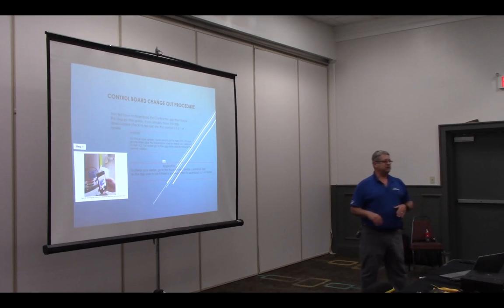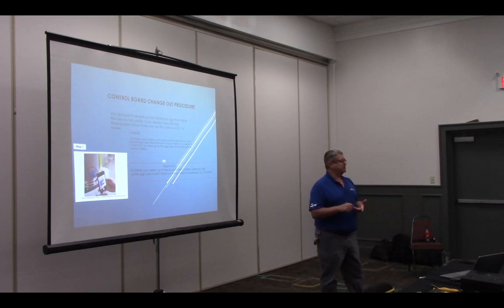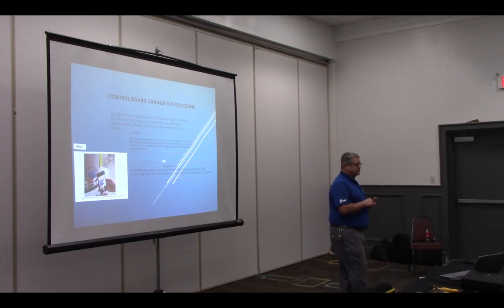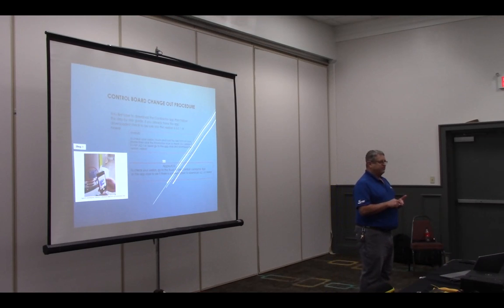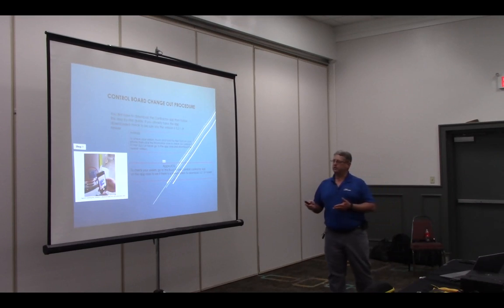If you put any of this equipment in, I would recommend updating the boards prior to installing them. With the 15 and 16 SEER, if you install a 3-ton or a 5-ton, you have to update the outdoor board, because there have been updates to those two pieces of equipment, the 3-ton and the 5-ton, 15 and 16 SEER straight cool or heat pump. Okay? So we're going to go through this.